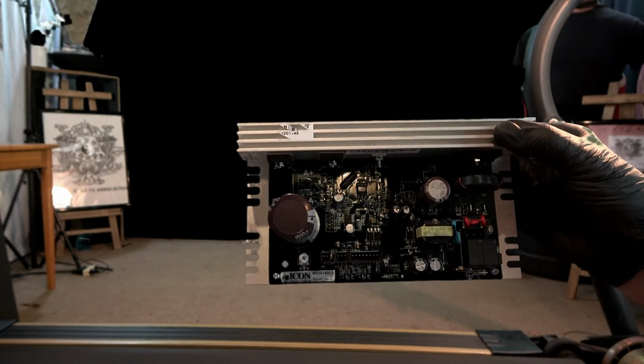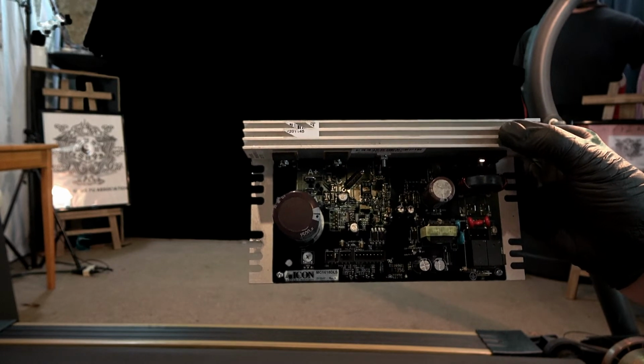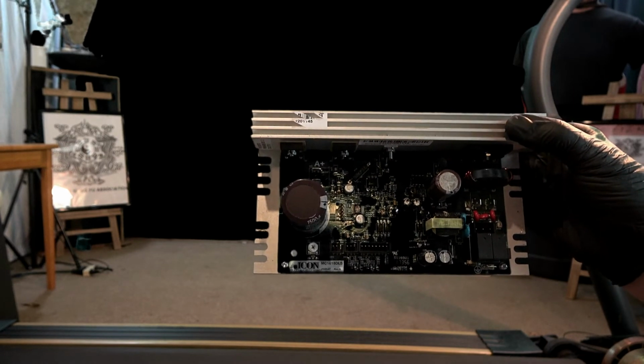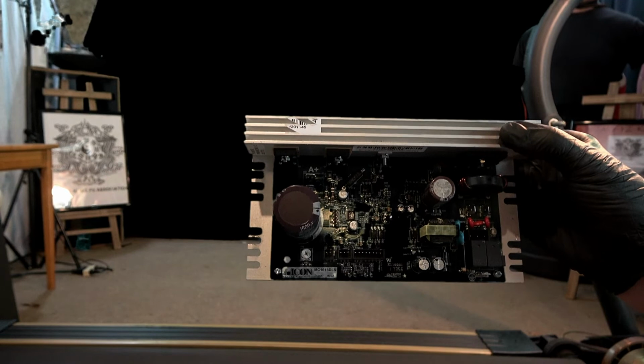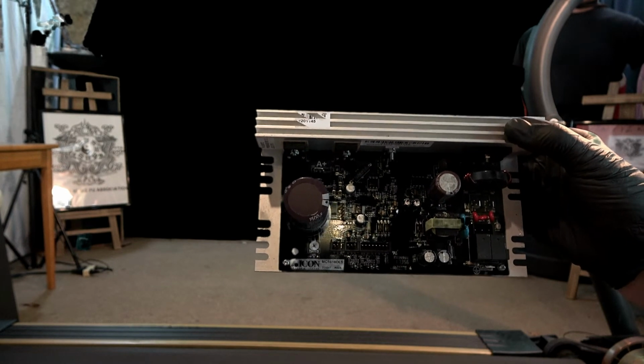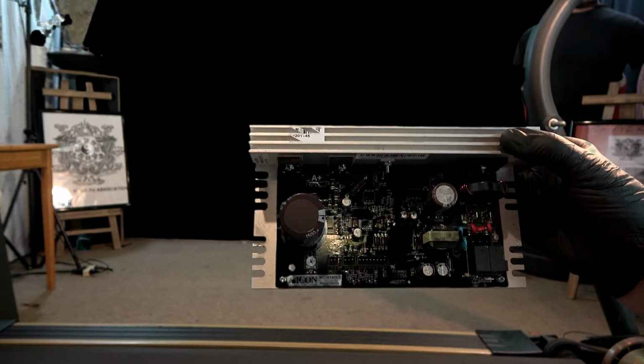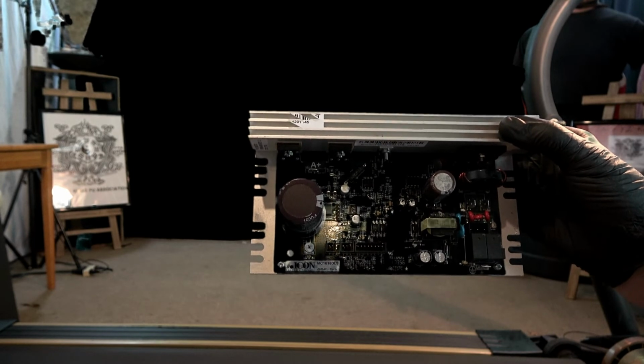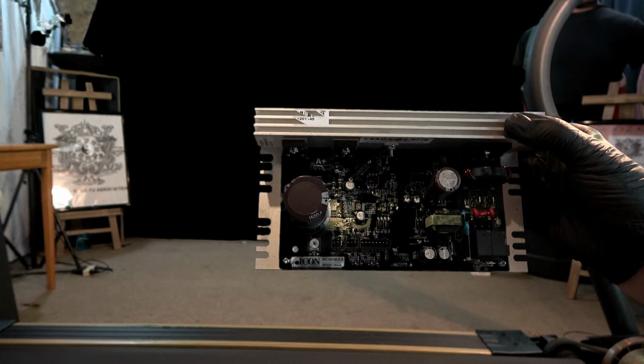So there's a bit of wiring configuration difference. You really don't even need to use the thermal breakers inside the motor, I've been doing this 30 years and never seen it trip, but it's there for a reason, so since you have it, we'll wire it back into our new board.